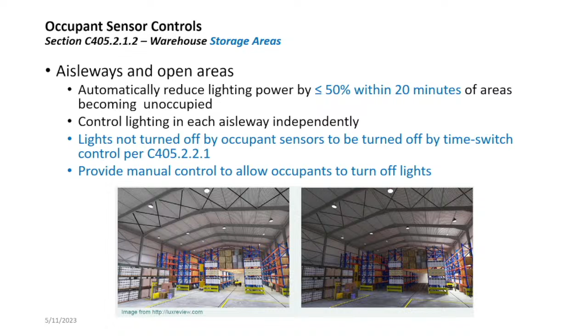Please. Brent, in regards to NEC 2020 comparison to the IECC for this, is there something that's trumping the other, or is this coming from the NEC? I don't think NEC really has a lot of mandatory lighting controls in it, does it? The only place that it really overlaps is in electrical rooms, where it says that the electrical room cannot be automatic only. You have to be able to turn it on and it stays on while the guy's in there working. So that's the only place that really gets into lighting control. I'm just kind of wondering how the IECC would compare, because you've got NEC and IECC, so we're trying to compare the two. Kind of completely different scopes.